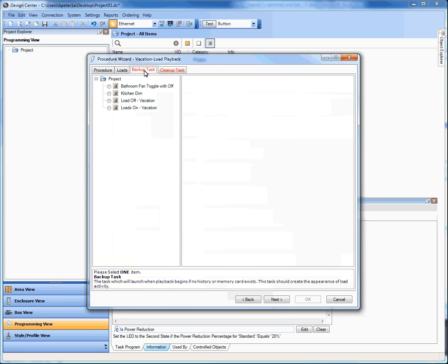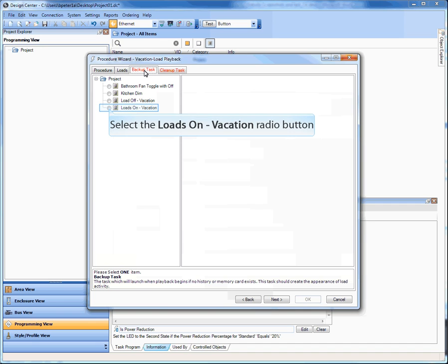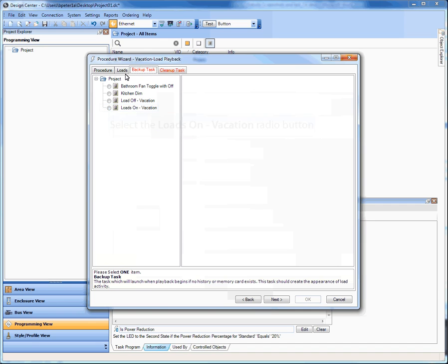It's actually tracking the loads — whether it's a button press, a touchscreen press, a timer, or a sensor — anything that happens to that load, we memorize and put into the log. It's important to note the tabs called Backup Task and Cleanup Task. The logs are not stored directly on the controller anymore; in Design Center 3.0 we've started storing logs on the SD card so we can store a lot more information for a longer period.